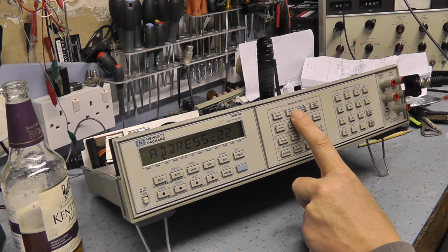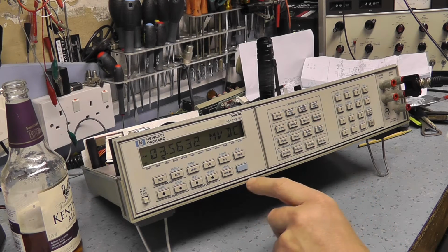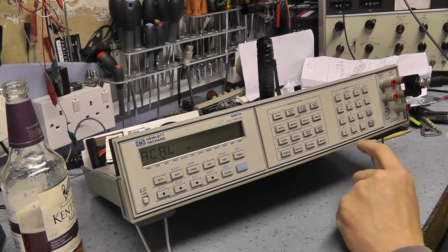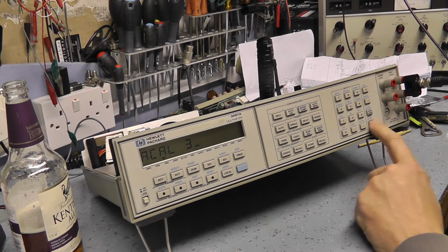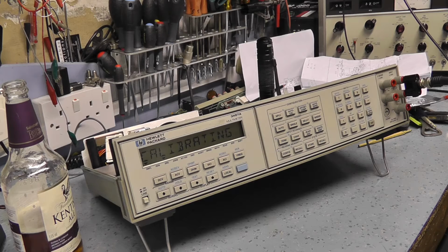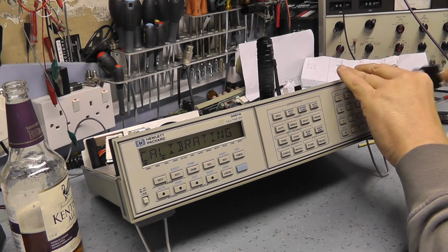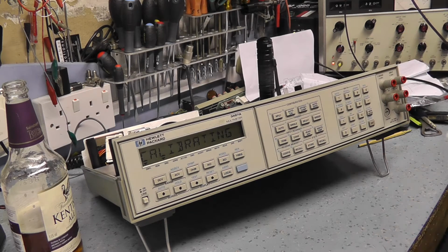That procedure I've just shown you was to show you the in-depth error message. So it's as simple as this: you press auto cal, press 3 for AC, and press enter, and it's running the calibration routine. Well, it will fail simply because there's still something wrong with it.